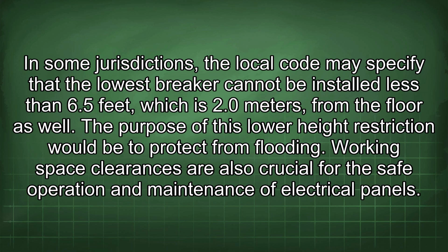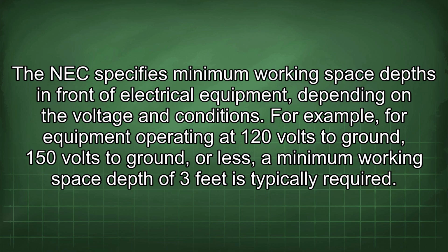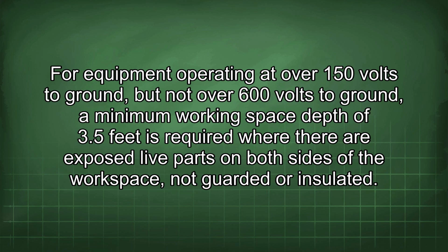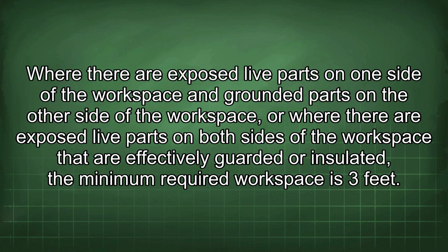Working space clearances are also crucial for the safe operation and maintenance of electrical panels. The NEC specifies minimum working space depths in front of electrical equipment depending on the voltage and conditions. For example, for equipment operating at 120 volts to ground, 150 volts to ground, or less, a minimum working space depth of 3 feet is typically required. For equipment operating at over 150 volts to ground, but not over 600 volts to ground, a minimum working space depth of 3.5 feet is required where there are exposed live parts on both sides of the workspace, not guarded or insulated. Where there are exposed live parts on one side of the workspace and grounded parts on the other side of the workspace, or where there are exposed live parts on both sides of the workspace that are effectively guarded or insulated, the minimum required workspace is 3 feet.